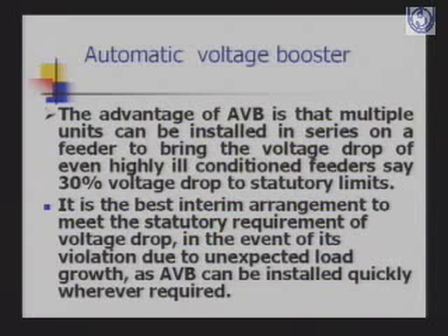Thank you, Rakhi. So we were talking about voltage boosters, automatic voltage boosters. We had said that the automatic voltage booster is like a load tap changer. The advantage of automatic voltage booster is that multiple units can be installed in series on any feeder to bring the voltage drop of even highly ill-conditioned feeders, say 30%, to statutory limits.